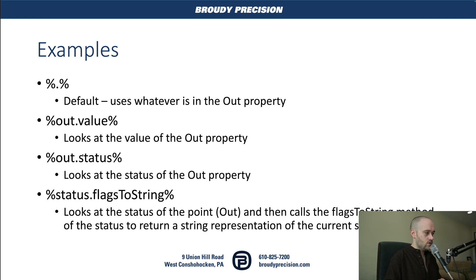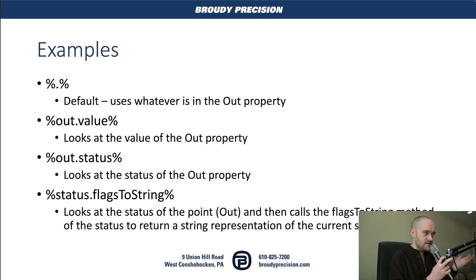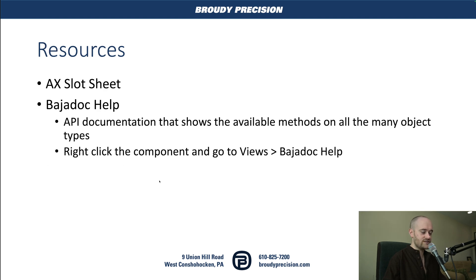Another example is out.status — same idea as out.value except now we're looking at the status instead of the value. Then there's status.flagsToString, which is quite a bit more complicated. We're looking at the status of the point and calling a flagsToString method, which is part of the status object. That method does work to convert the status to a human-readable string that looks nicer than the default out.status output.